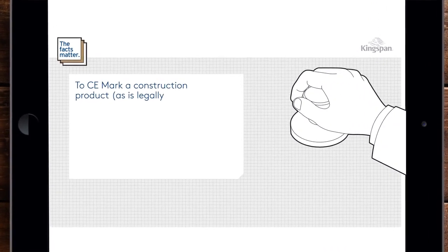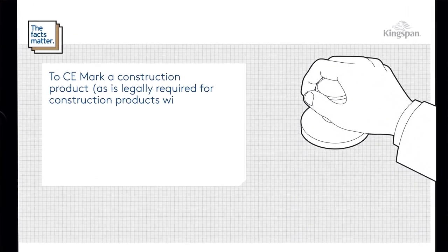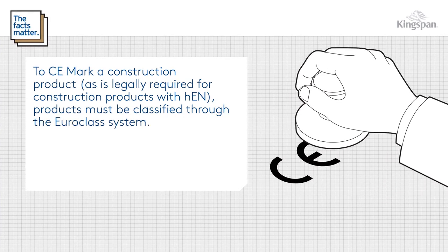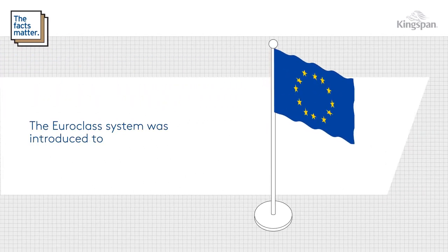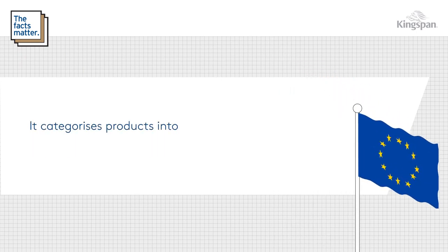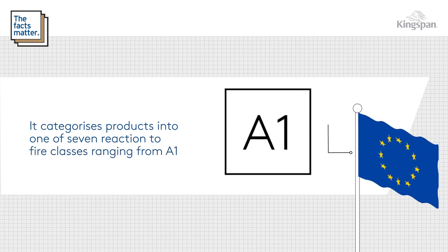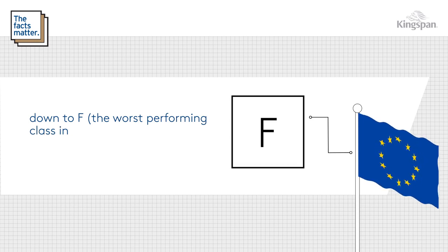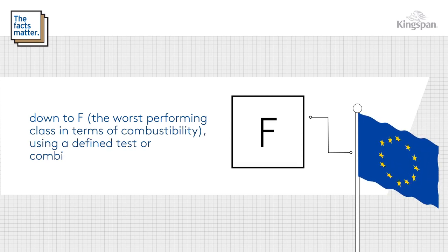To CE mark a construction product, as is legally required for construction products with HEN, products must be classified through the Euroclass system. The Euroclass system was introduced to harmonise standards across the EU. It categorises products into one of seven reaction to fire classes, ranging from A1, non-combustible, down to F, the worst performing class in terms of combustibility, using a defined test or combination of tests.